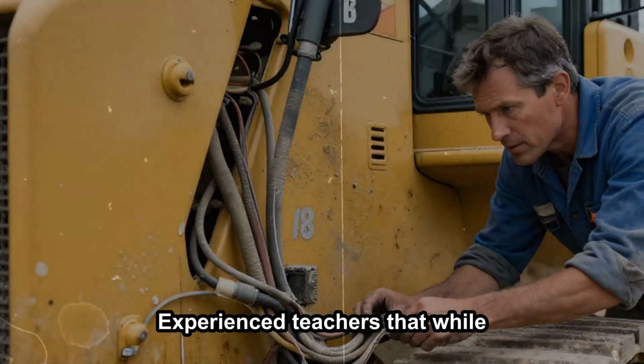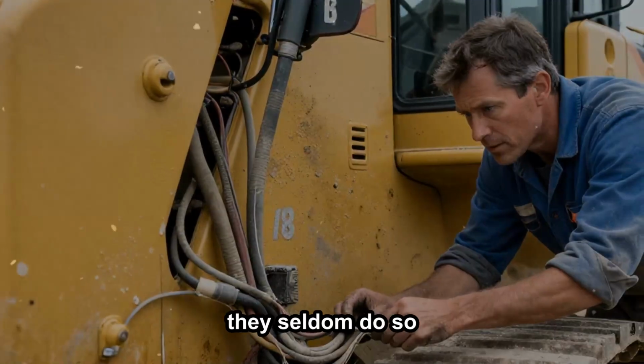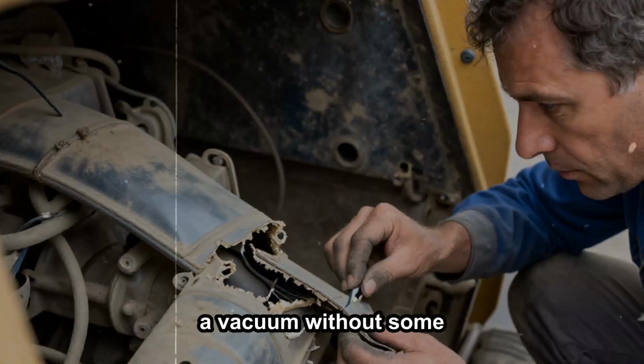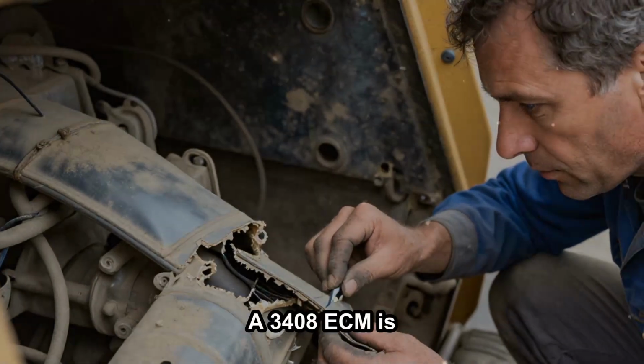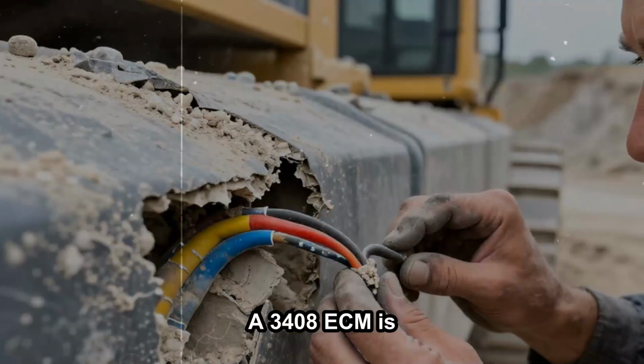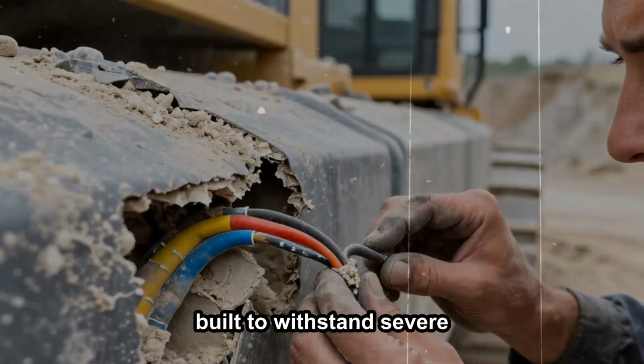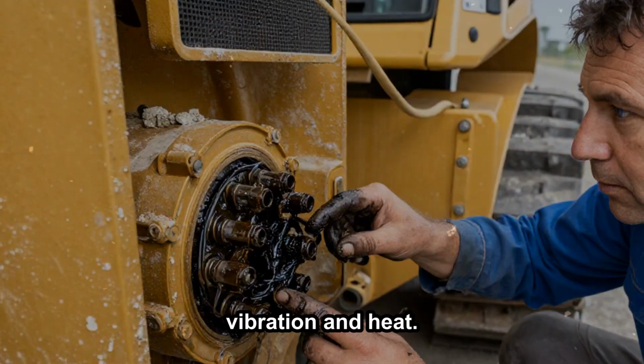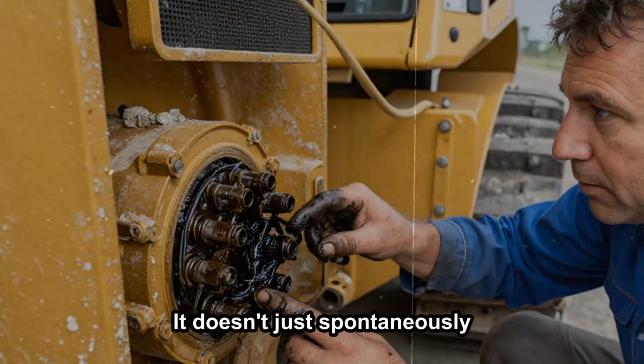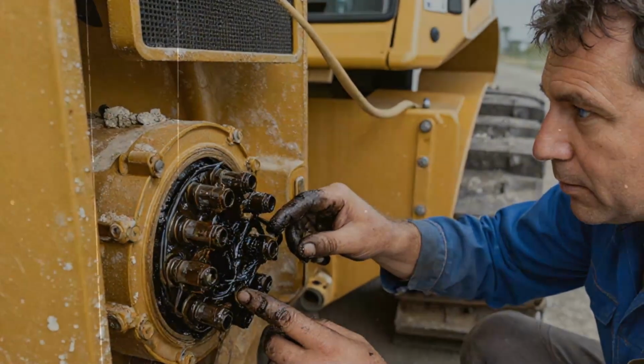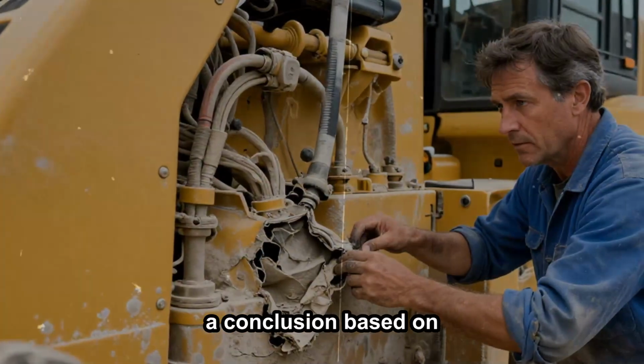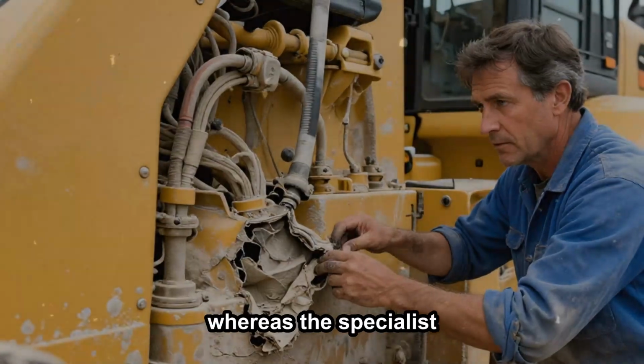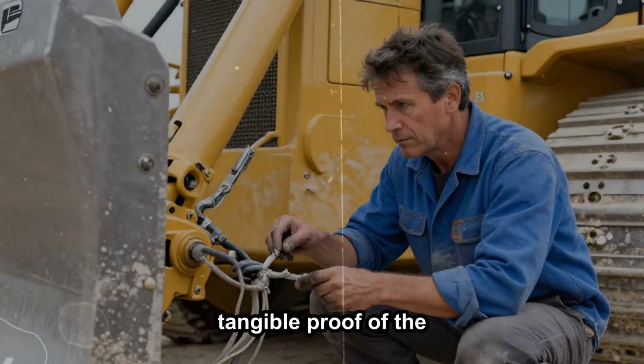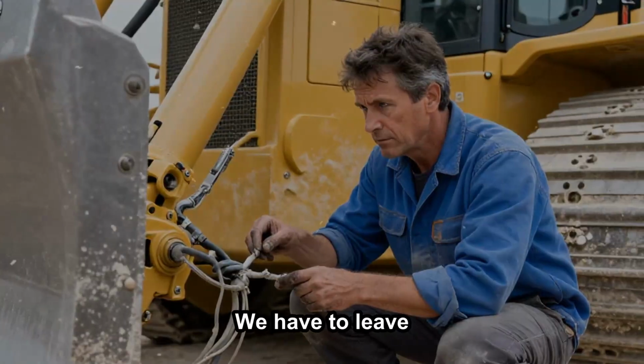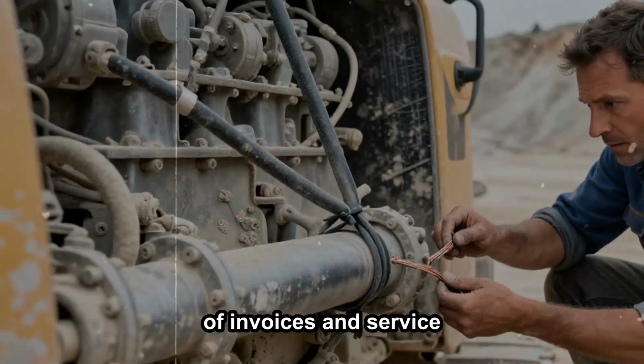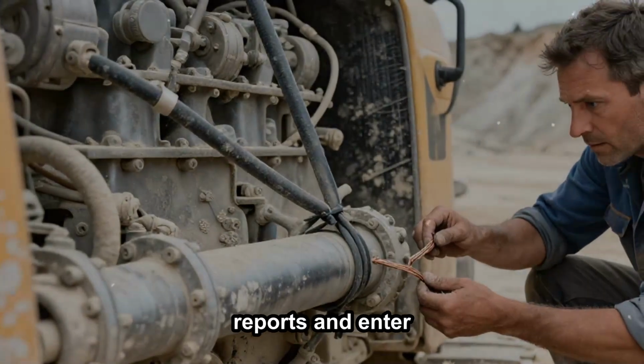Experience teaches that while electronic components can fail, they seldom do so in a vacuum without some external trigger. A 3408 ECM is a ruggedized, potted device built to withstand severe vibration and heat. It doesn't just spontaneously expire without a reason. The dealer's report was a conclusion based on a lack of information, whereas the specialist was determined to find tangible proof of the fault.